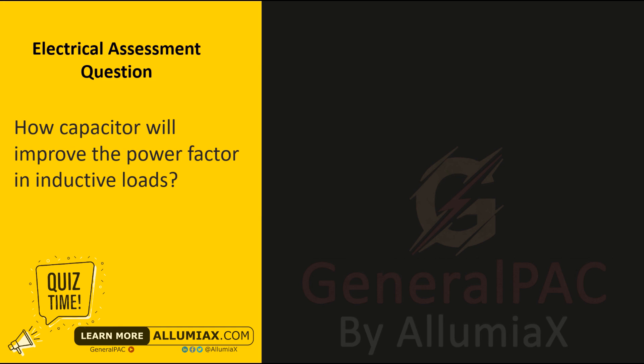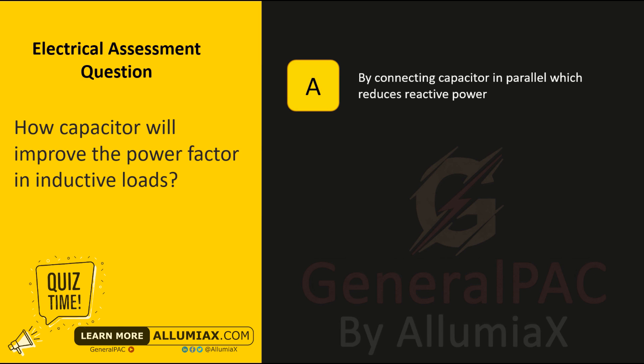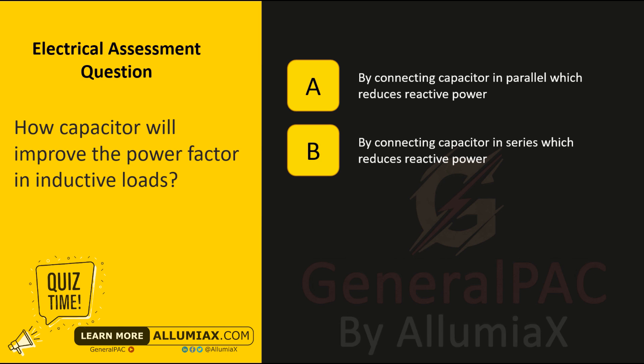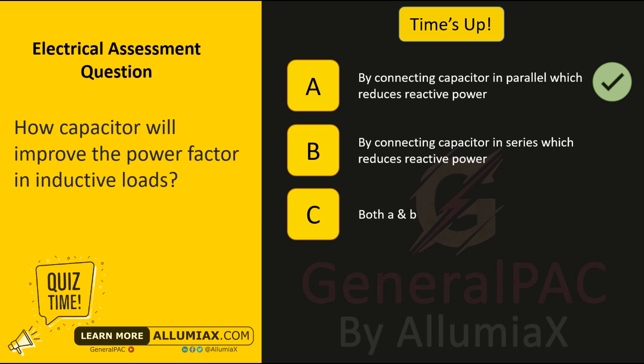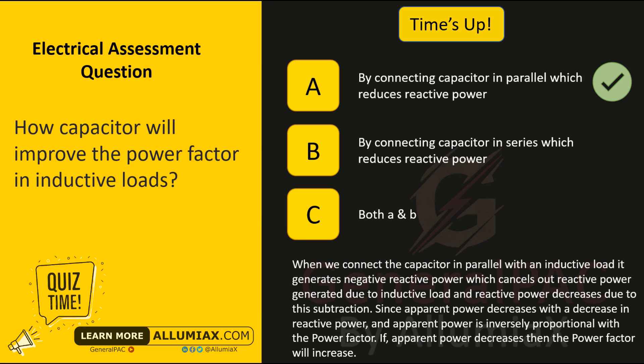How will a capacitor improve the power factor in inductive loads? A: By connecting the capacitor in parallel, which reduces reactive power. B: By connecting the capacitor in series, which reduces reactive power. C: Both A and B. Time's up. The answer is A: By connecting the capacitor in parallel, which reduces reactive power. When we connect the capacitor in parallel with an inductive load, it generates negative reactive power, which cancels out the reactive power generated by the inductive load. Since apparent power decreases with a decrease in reactive power, and apparent power is inversely proportional to the power factor, if apparent power decreases, then the power factor will increase.